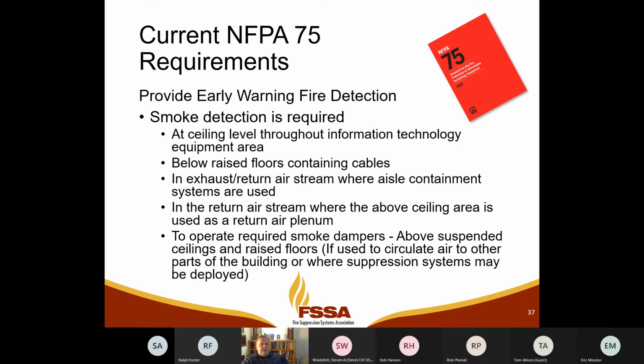So to provide early warning fire detection, smoke detection is required in a data center at the ceiling level throughout the IT equipment level. So we're not getting rid of that. We've got to have smoke detection there. We need to have it below raised floors containing cables, and that's what it says. If you've got a raised floor system and it contains cables, then it needs smoke detection.